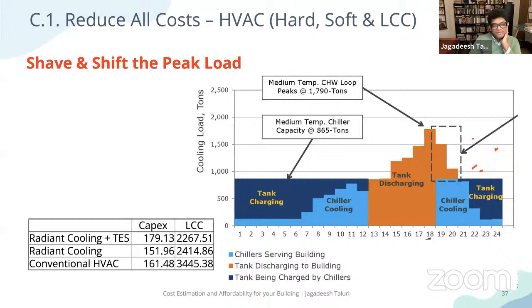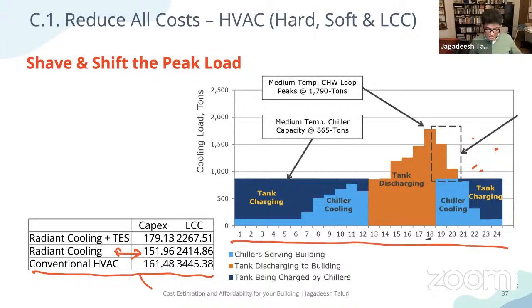So for example, let's say in this scenario the conventional HVAC system costs 161 lakh rupees, and we decided that a radiant cooling system would cost much lesser. But because of operational problems, say we're not getting electricity during peak hours. If you look at this line, from 0 to 24 hours, this is the operational cycle of the building during the daytime, say 10 to 7. This profile is the cooling demand load profile. The amount of cooling energy, or tonnage of chiller required to cool the building at its peak, decides the chiller plant sizing.